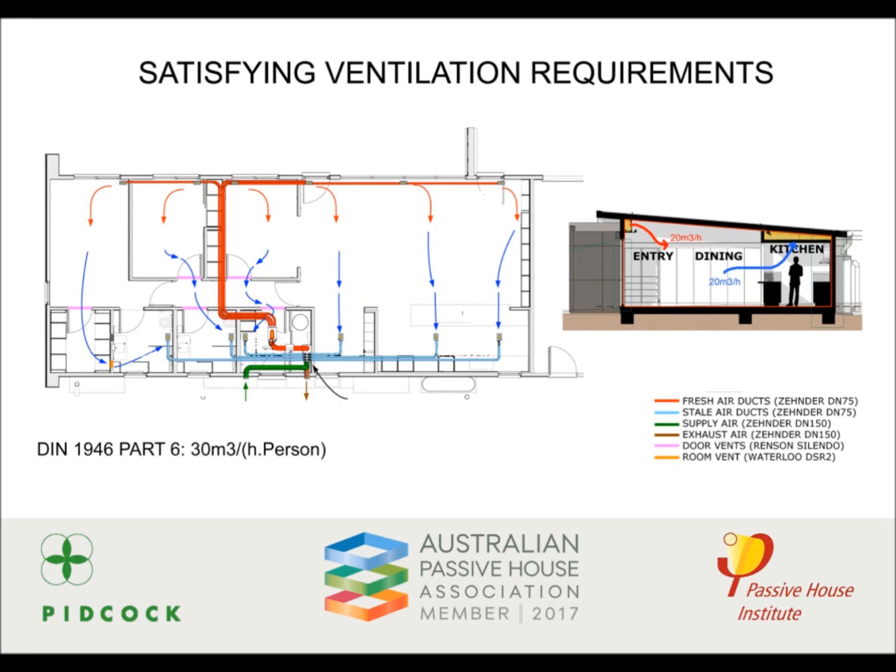An important part of a certified Passivhaus is the ability to deliver fresh air to all the house all the time. Harley devised a simple but ingenious mechanical ventilation system. Fresh external air is brought in from the south and enters the heat exchanger, where it takes all the heat from the exhausting air and heads over to the northern bulkhead, and it is dispersed throughout the house. This air is eventually extracted through extracts in the southern bulkhead, and any heat that's gained is handed over to incoming fresh air in the heat exchanger again, and the mechanical ventilation cycle goes on.